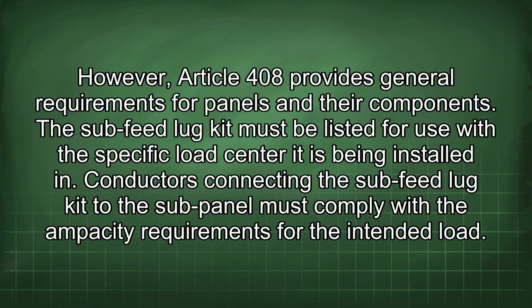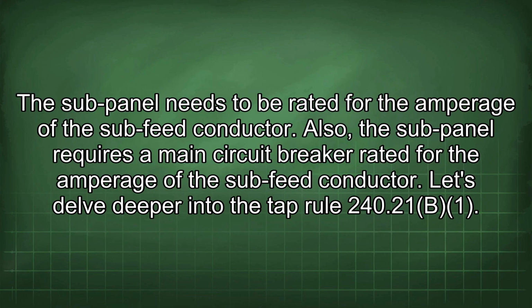The sub-feed lug kit must be listed for use with the specific load center it is being installed in. Conductors connecting the sub-feed lug kit to the sub-panel must comply with the ampacity requirements for the intended load. The sub-panel needs to be rated for the amperage of the sub-feed conductor. Also, the sub-panel requires a main circuit breaker rated for the amperage of the sub-feed conductor.